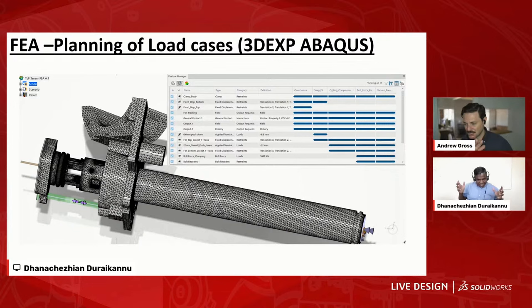Similar mechanism, but it goes into the anesthetic agent within a sub-assembly with the liquid, and so many interfaces are occurring. That's why vapor pressure is key for us. It should not fail when the vapor pressure is acting on all the surfaces of this product - that's one of the failure modes.